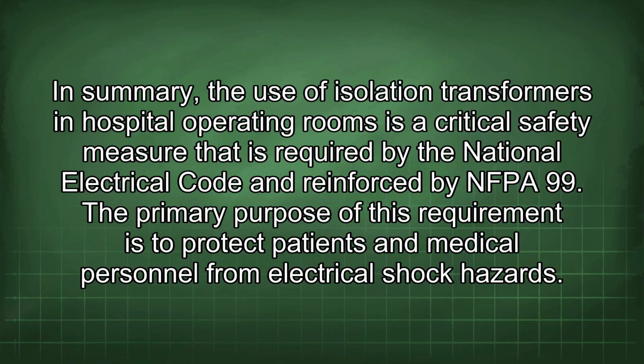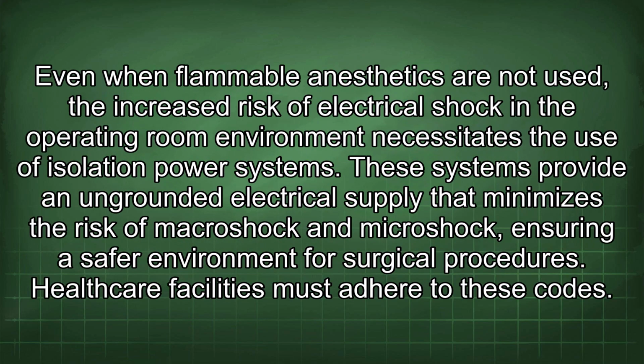In summary, the use of isolation transformers in hospital operating rooms is a critical safety measure that is required by the National Electrical Code and reinforced by NFPA 99. The primary purpose of this requirement is to protect patients and medical personnel from electrical shock hazards. Even when flammable anesthetics are not used, the increased risk of electrical shock in the operating room environment necessitates the use of isolation power systems. These systems provide an ungrounded electrical supply that minimizes the risk of macroshock and microshock, ensuring a safer environment for surgical procedures. Healthcare facilities must adhere to these codes.